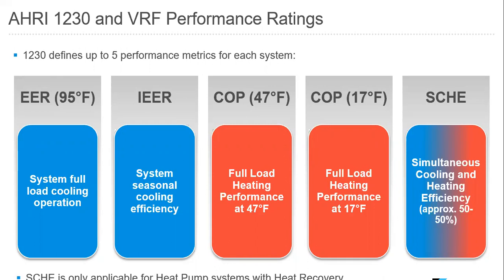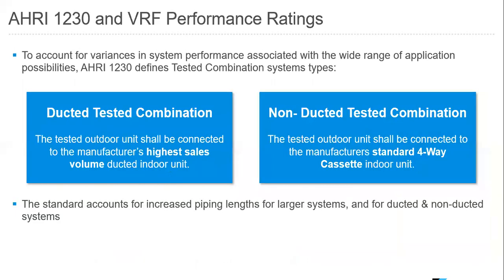By the way, SCHE is only applicable for heat pump systems with heat recovery. AHRI 1230 and VRF performance ratings. To account for variances in system performance associated with a wide range of application possibilities, AHRI 1230 defines the tested combination system types. So there are actually 2 different types of systems. There's a ducted tested combination and a non-ducted tested combination. So when you review the AHRI 1230 ratings for a given manufacturer, you'll see the terms ducted and non-ducted.